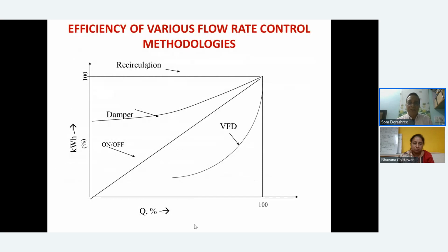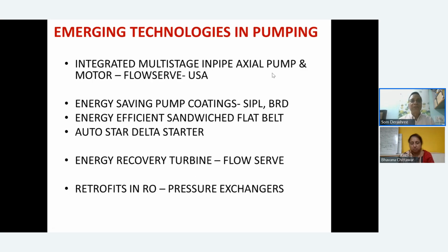Of course, we have seen that when you control the flow, VFD is the most efficient option. Then you have on-off control, then you have damper control, and you have recirculation. That is no power saving. Actually, it recirculates back into the suction. I'll share a typical application with you in a few case studies here.